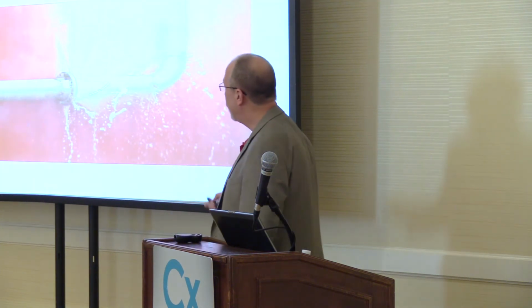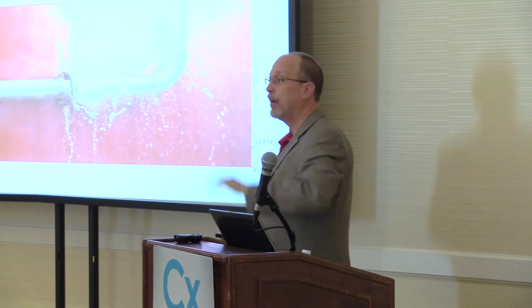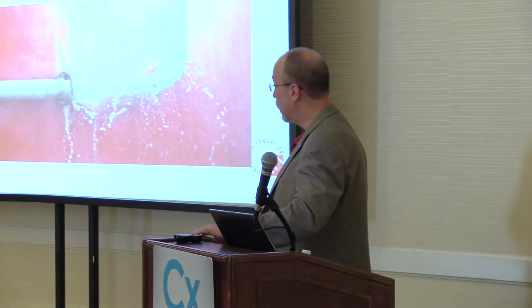So what they're doing is putting flow meters in primary lines and they're just tying into the building automation system or just tying in a direct line that has a low flow cutoff or a high flow cutoff. If something's unusual, someone gets a phone call, an alarm goes off there. So leak detection, primary, brand new giant application there, sponsored by the insurance industry.